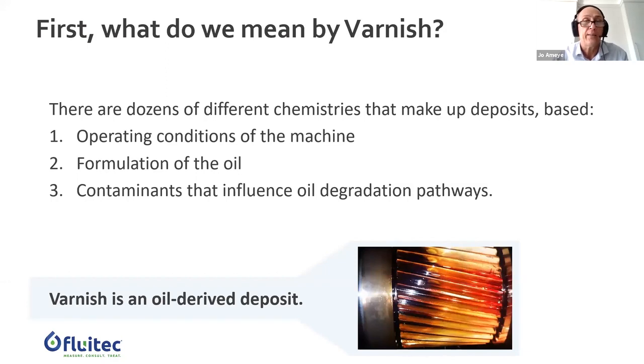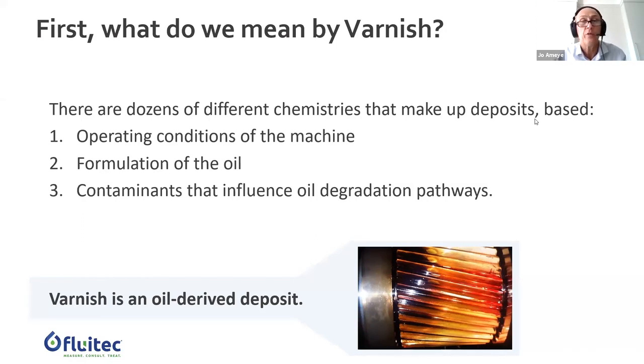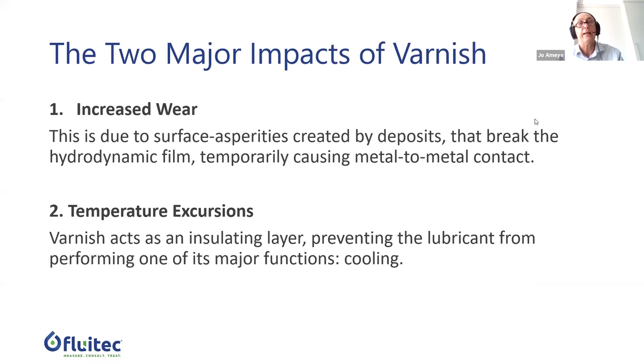One thing you certainly cannot do is generalize — there are really dozens of chemistries in varnish. It is very dependent, first of all, on the operating conditions of the equipment: think about whether it is a steam turbine working in base load versus a compressor on a gas turbine running 24/7 at peak load. It also depends on the formulation of the oil — consider the evolution that has been going on in the last decade — and last but not least, contamination, which influences all degradation and oxidation.